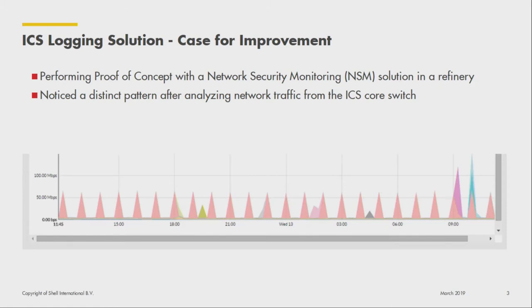About two years ago, all this network visibility equipment came out and I thought we have to get this in our plants. If you asked me as an asset owner what my biggest concerns were, I'd say: I don't know what's in my environment. So we put an NSM tool out in our plant, hooked it up to our core switch, and started seeing all this information. We noticed substantial traffic in our network at the L2/L3 level — and after looking at it for a couple of days, we didn't really know what it was. Come to find out, this was us doing harm to ourselves.